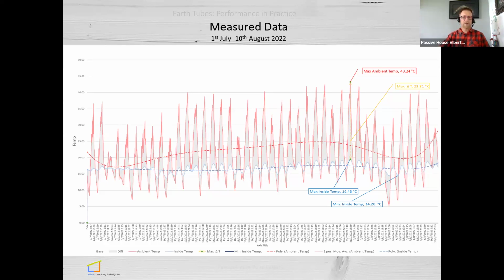Do you want to explain the HVI defrost mode versus the PHI HRV defrost modes again? Just to make sure, some people weren't clear on that. Okay. So the Passive House certified units don't have a defrost mode, which means the heat exchanger can freeze. Whereas the HVI units have a defrost mode where a lever stops the incoming air, and you route your stale air from inside the house through the heat exchanger to defrost it, and then back into the house. So during this time, you have a higher energy consumption. You don't have fresh air, and you don't have heat exchange or energy savings, right? So yeah, this is the main reason.